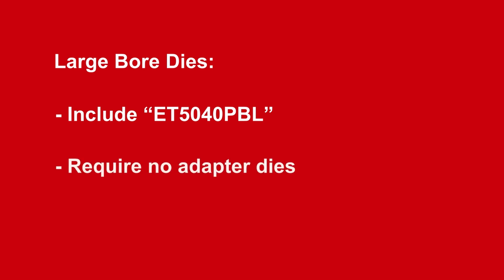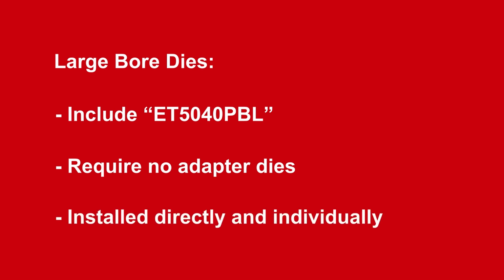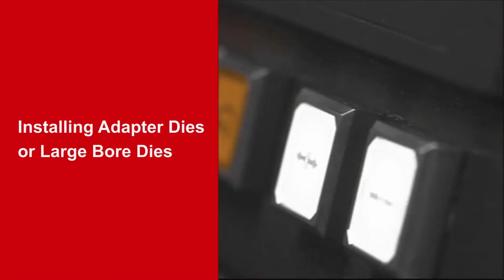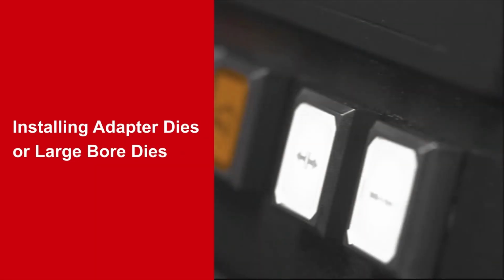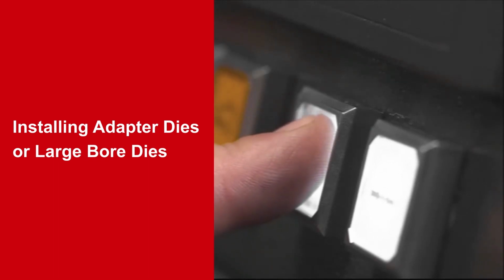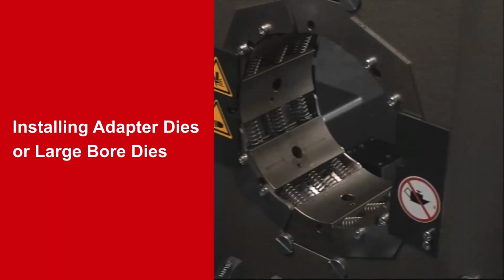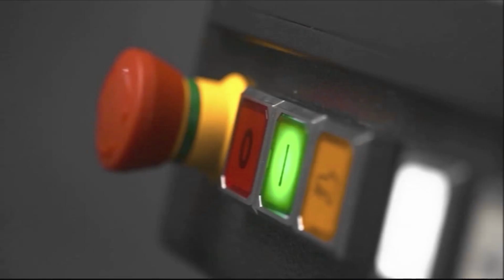ET5050 large bore dies are dies which include ET5040 PBL in their name string. The large bore dies do not require the ET5040C0001 adapter dies and are installed directly into the crimp head as individual die segments. To install the ET5040C0001 adapter dies or large bore dies, retract the crimp head completely. The sight holes should be exposed and accessible.